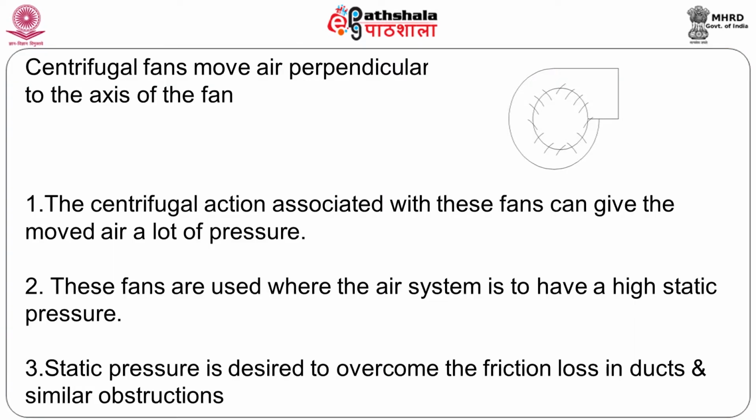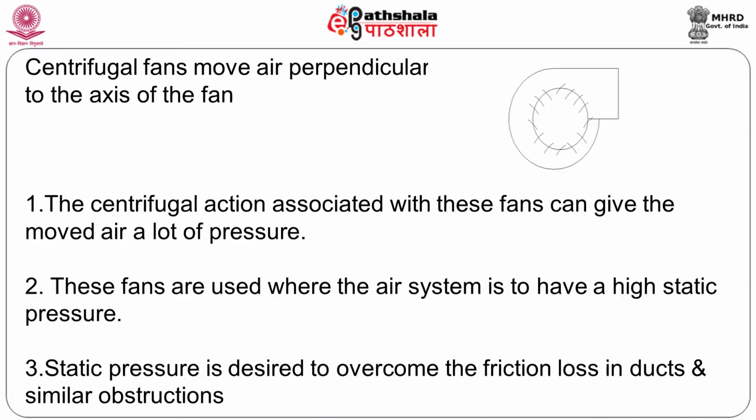So when you change from a propeller fan or an axial flow fan to a fan which requires filters, the next best thing you can do is to go in for a centrifugal fan. A centrifugal fan has more power. It uses the centrifugal force to make the airstream more powerful so that it can push its way through a filter. Now these fans obviously consume a little more horsepower, but they are required for that kind of duty.